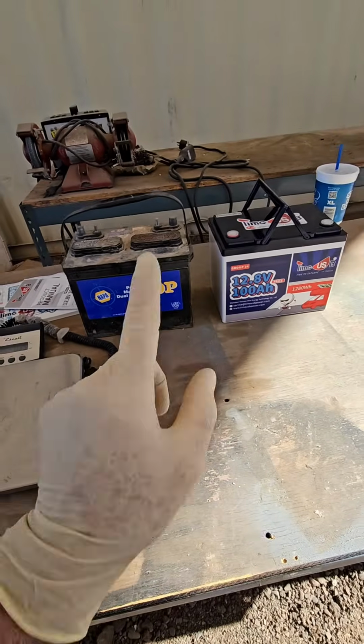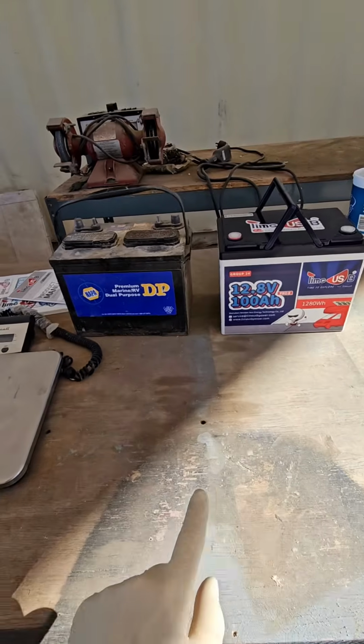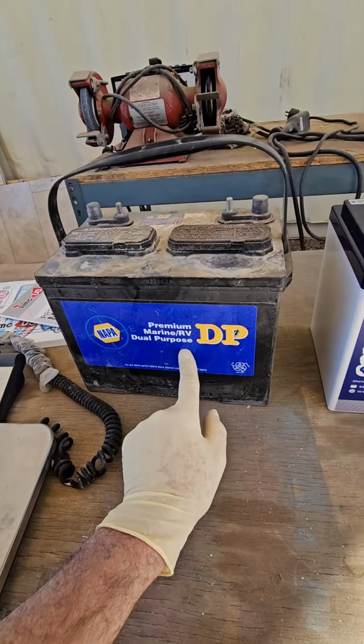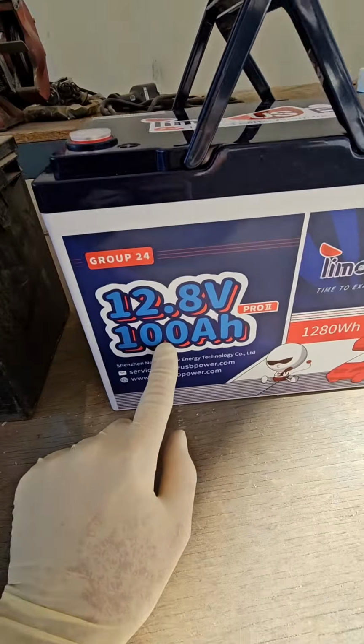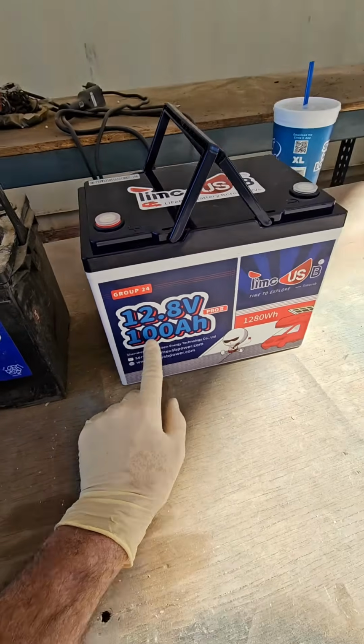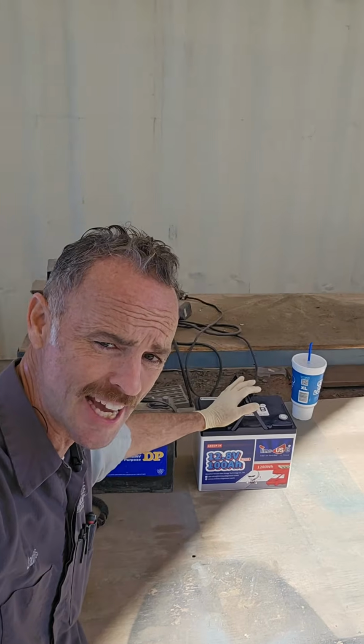Number 3, which might be the most important one, is capacity. Like I said, this has about 70 amp hours of capacity, while this one contains 100 amp hours. And remember, we're not supposed to use all the capacity on a lead acid battery, so about 40, maybe 45 amp hours compared to 100 amp hours of complete usable capacity.